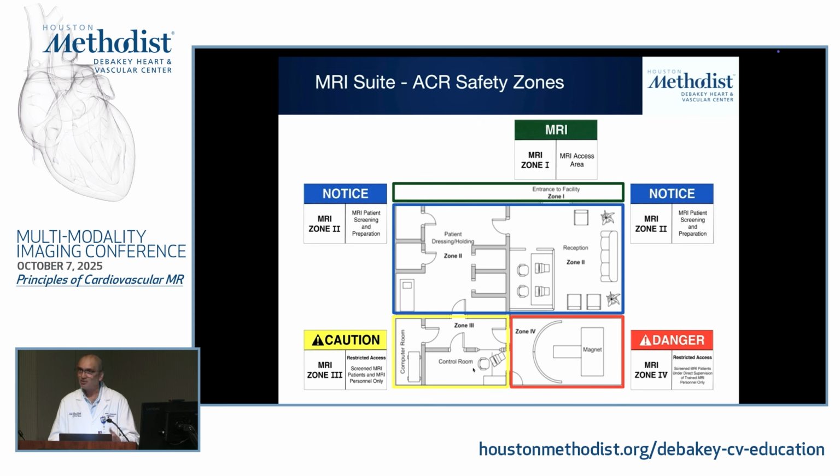That's a control room. If you've ever seen the tech scanning a patient, that's zone 3 right here. This is also controlled access, so nobody should be able to just wander into zone 3. And then the next zone is zone 2.